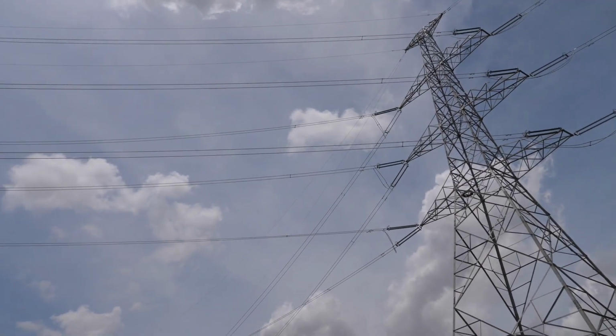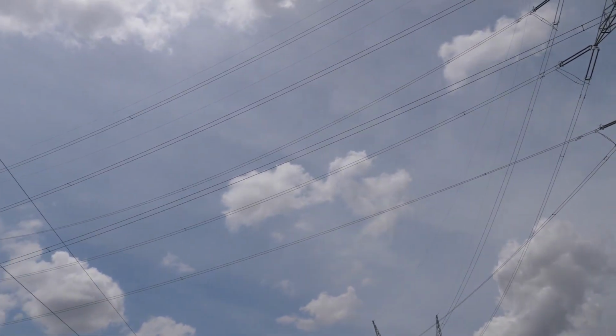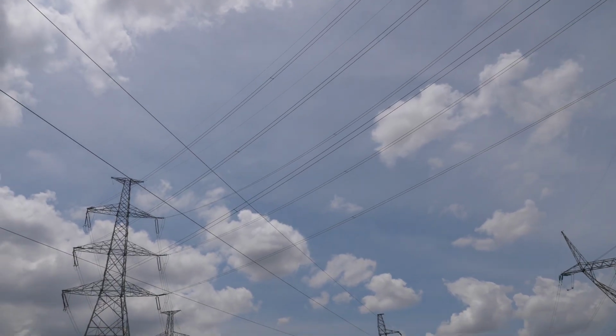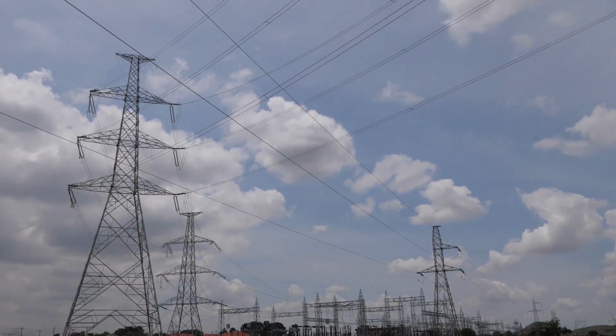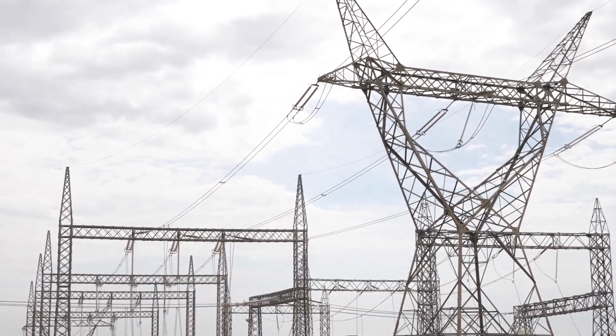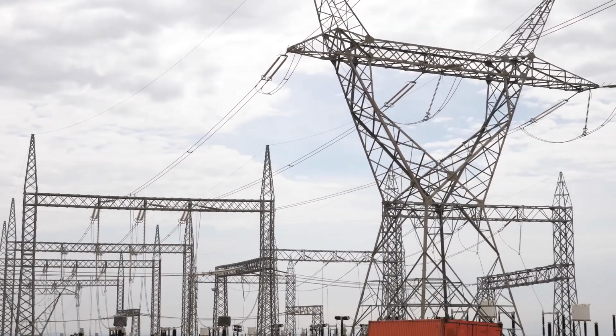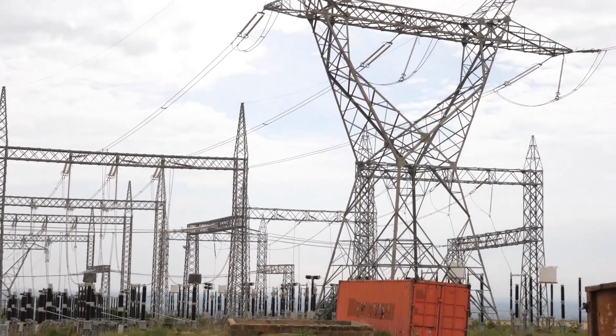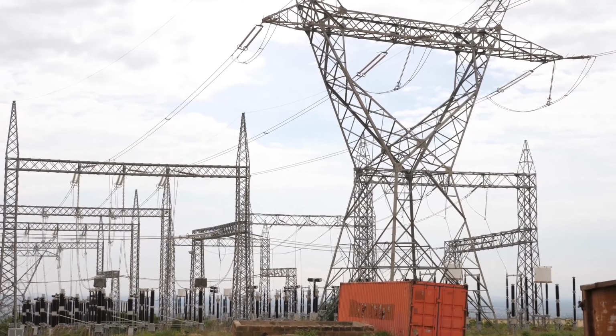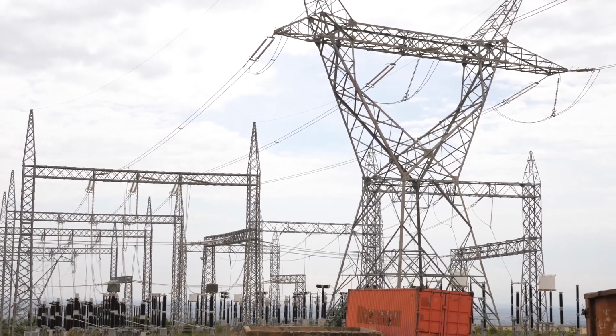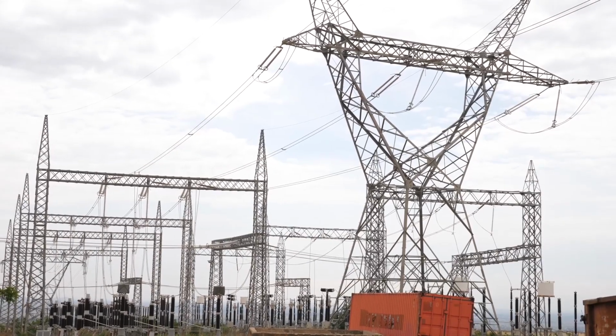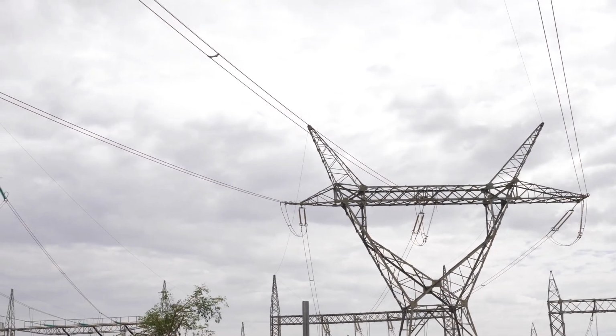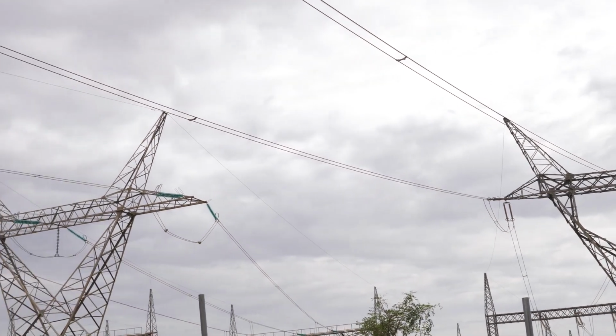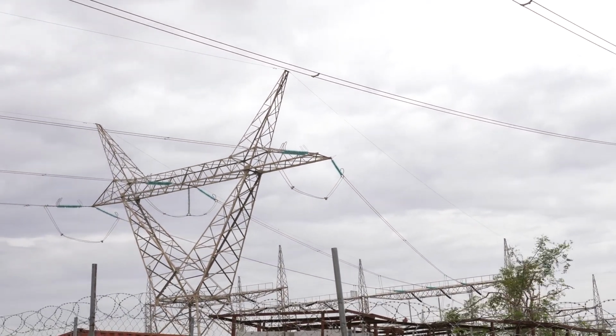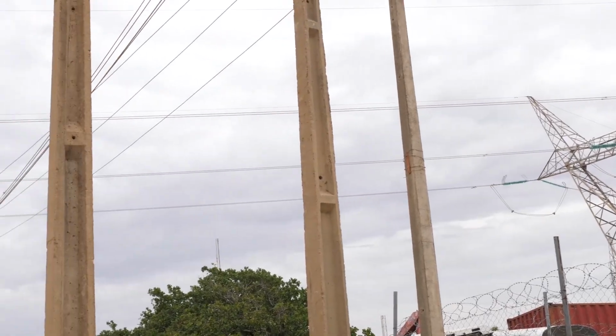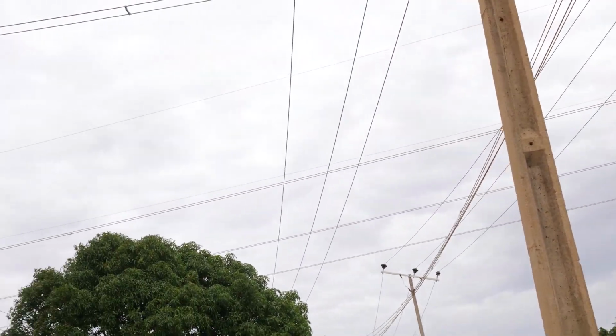There is also a 75 MVAR reactor installed at the 330-132-33 kV Katampe substation in Abuja and a similar one at the 330-132-33 kV Jos transmission substation in Plateau State. The reactor in Katampe regulates the voltage level on the 330 kV Shiroro hydropower station to the Katampe transmission line. Equally, the reactor at the Jos substation regulates the voltage level on the 330 kV Aper to Jos transmission line.